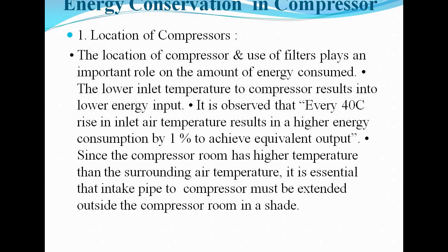So it is observed that every 4 degree centigrade rise in the inlet air temperature results in a higher energy consumption by 1% to achieve equivalent output. So if there is a 4 degree increase in the inlet temperature, then the energy consumption increases by 1%.